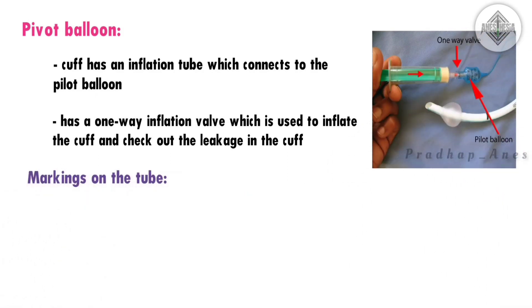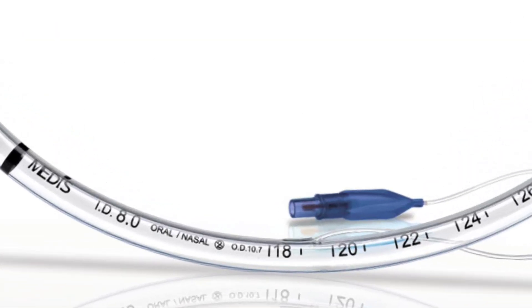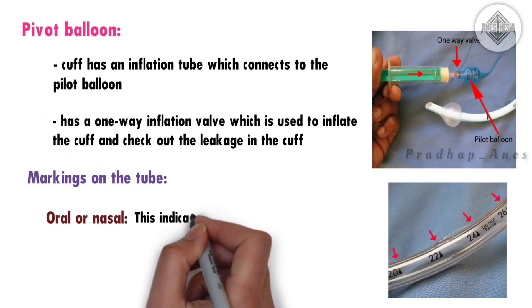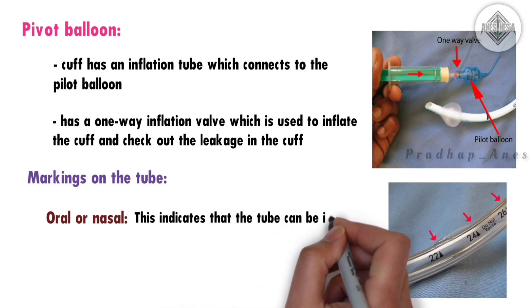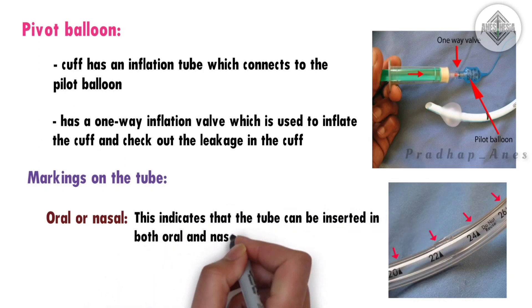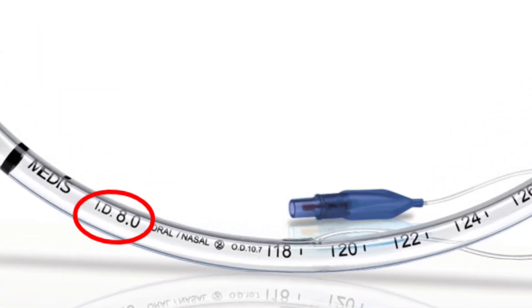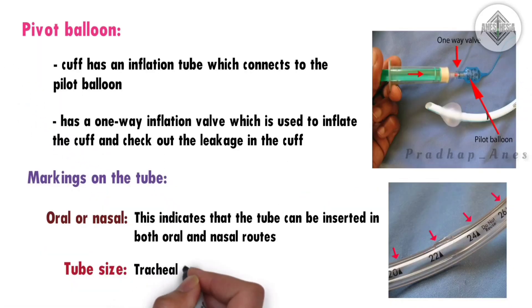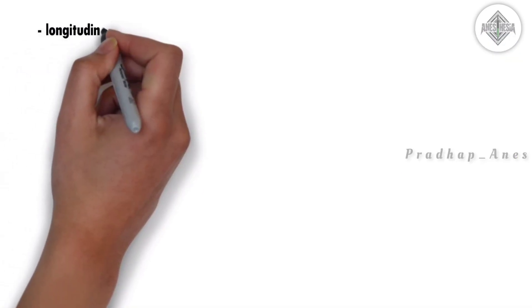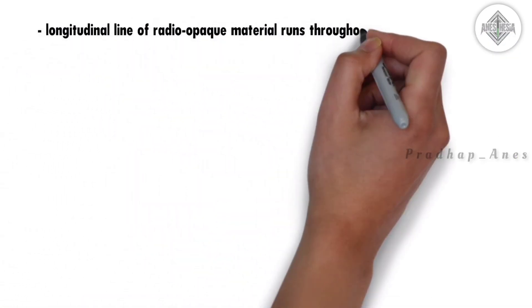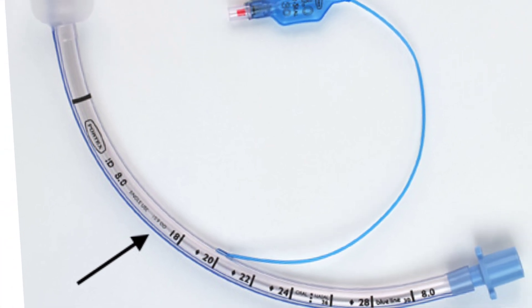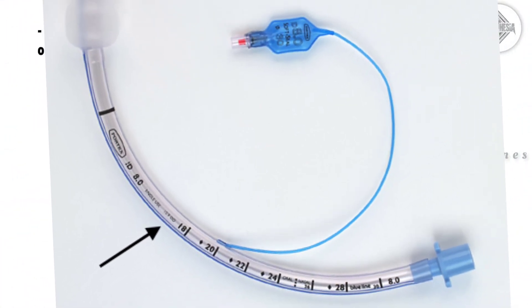Markings on the tube. First, you can see the words oral or nasal, which indicates that the tube can be inserted via both oral and nasal routes. Then we can see the tube size. Tracheal tube size is either in millimeters internal diameter (ID), or French scale size — three times the external diameter in millimeters. Finally, we have a longitudinal line of radio-opaque material that runs throughout the length of the tube for confirmation of correct placement from an X-ray.